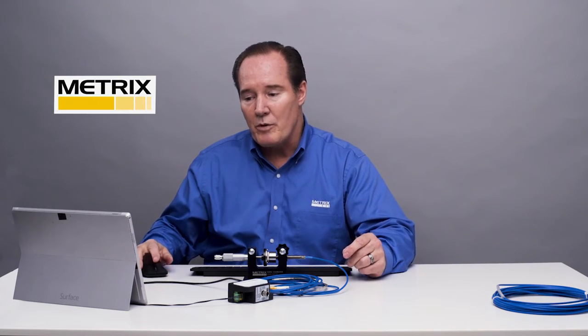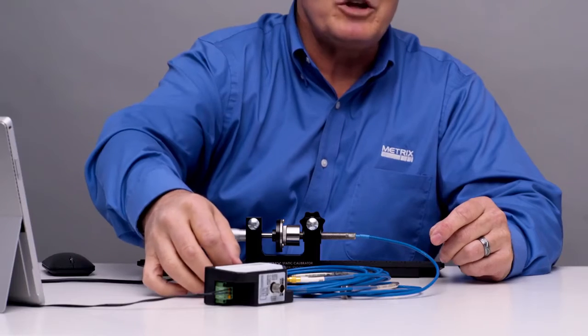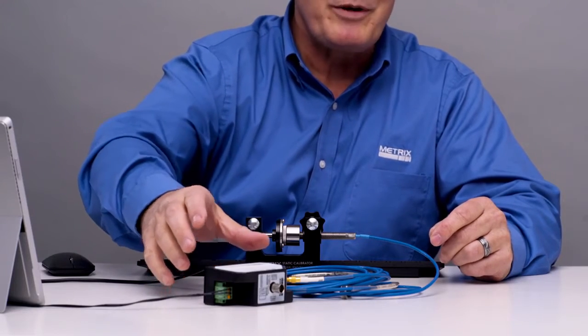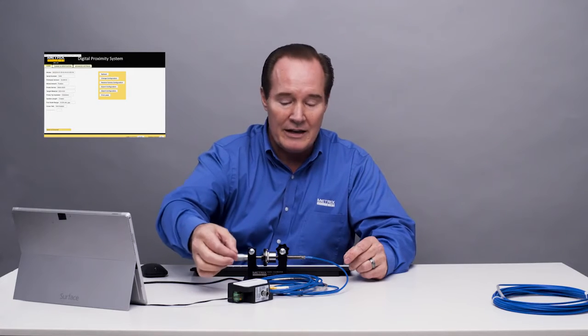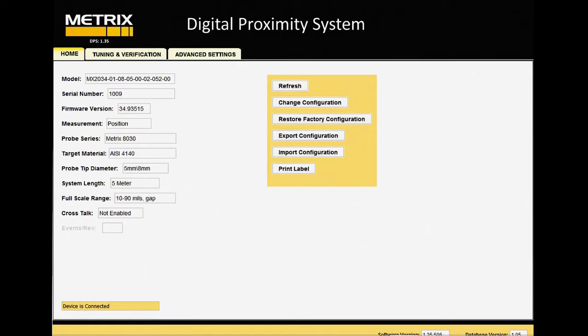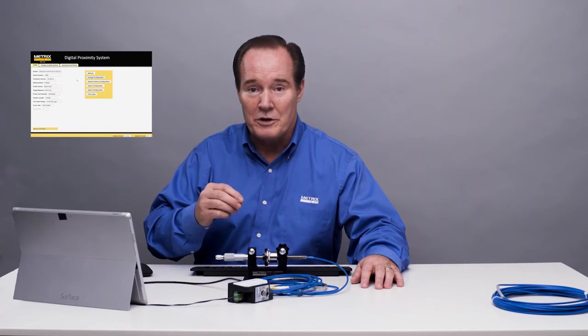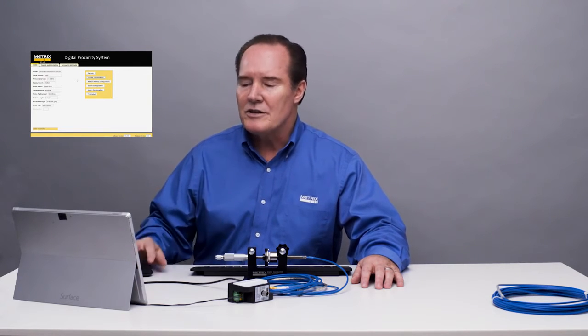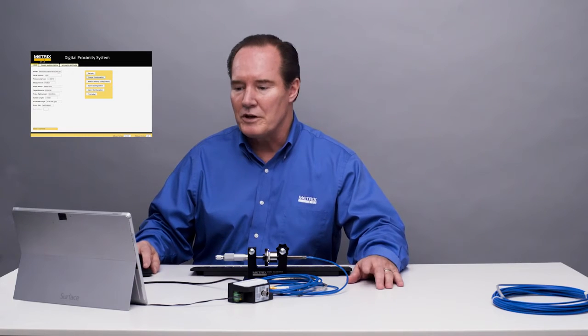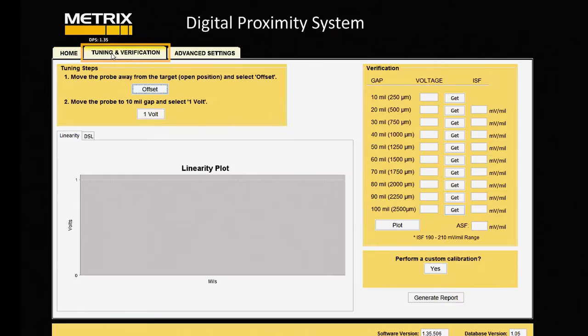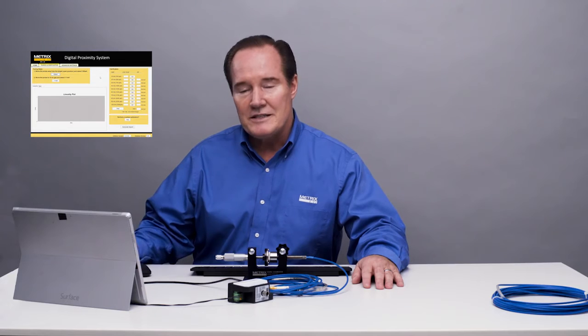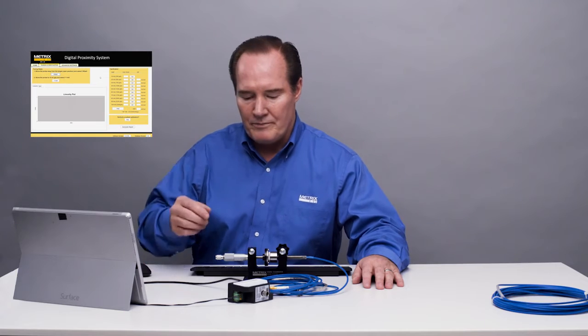So I'm going to start the software and I have it connected via the USB cable, which is normally covered by the DIN rail mounting, but I've removed that and now I'm connected to it. Before I change the configuration, let's just run it and see how it behaves. I think it's of interest to show you what it looks like if you didn't change the configuration. How linear is it? So let's go ahead and run it first without changing the configuration. So we'll just go to the tuning and verification step, and let's just go ahead and take data. And we'll take data every 10 mils, and let's just see what we get.